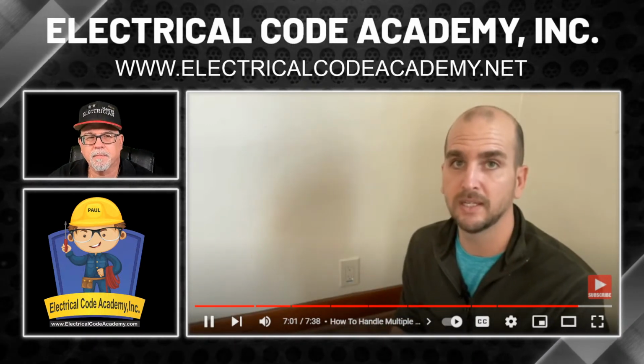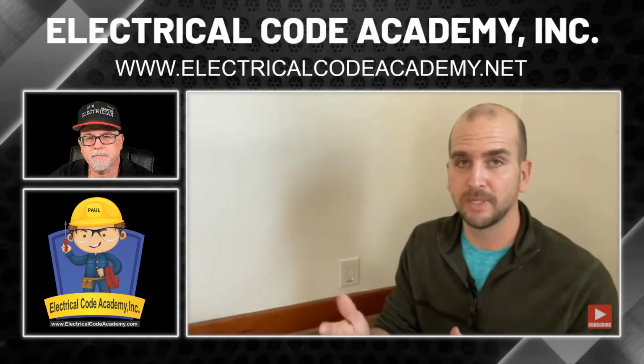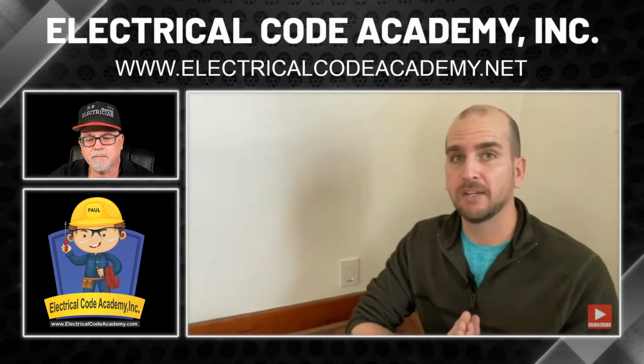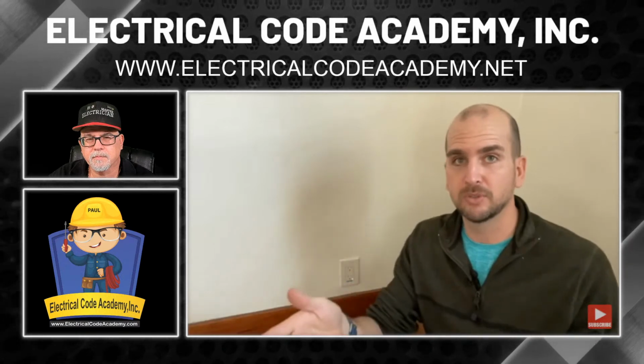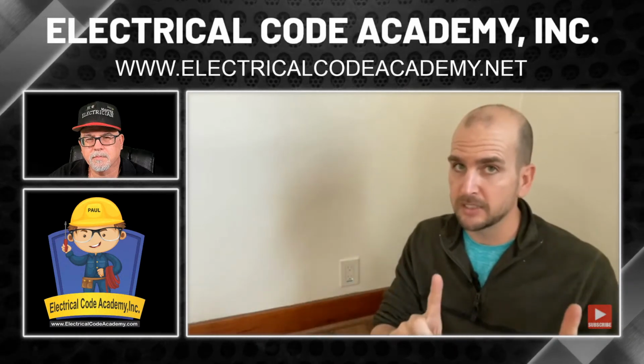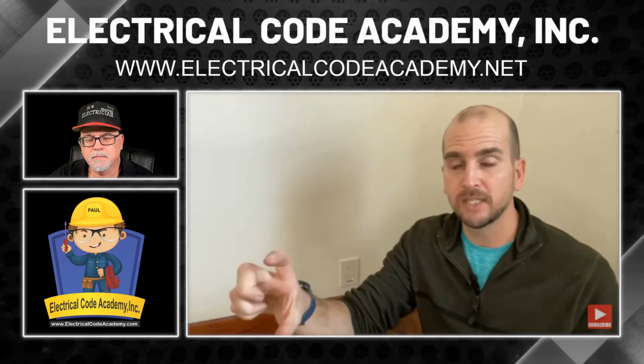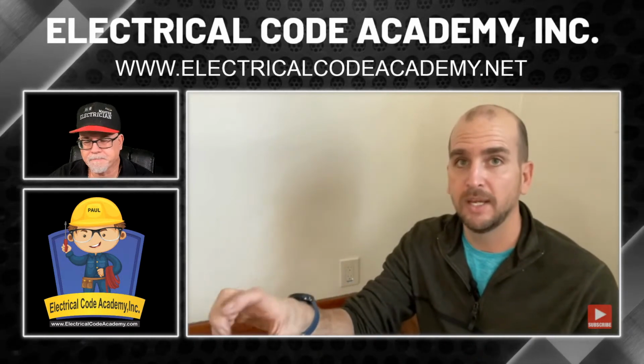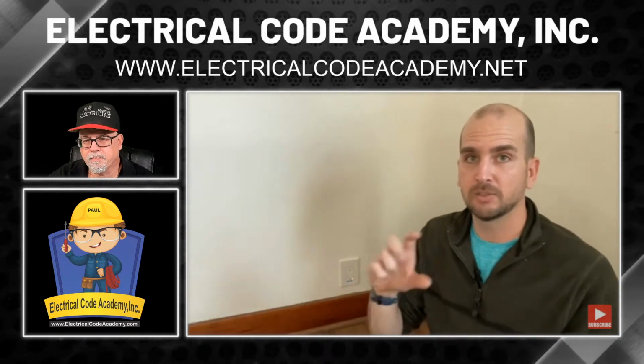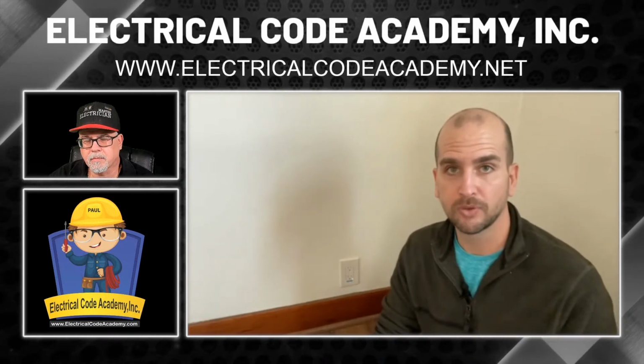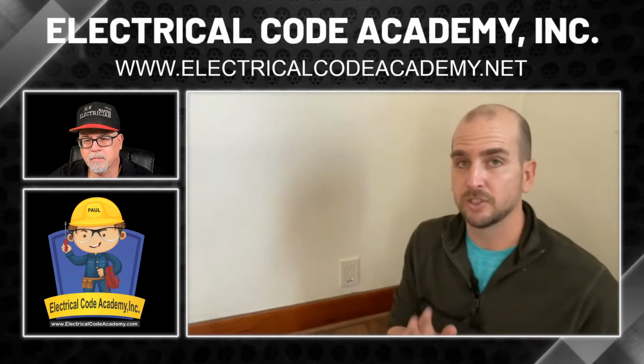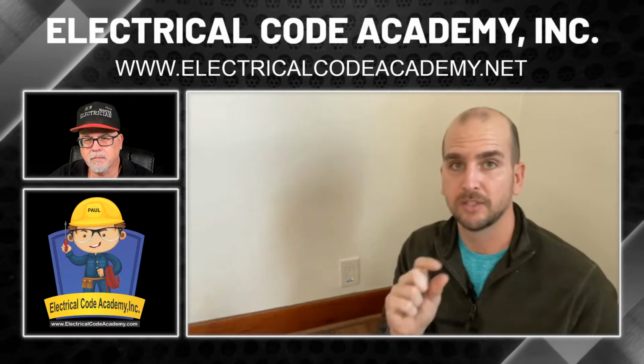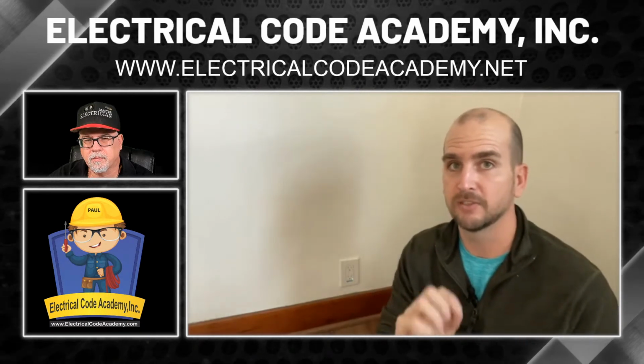As opposed to a GFCI. Now again, getting a little more complex, but I just wanted to let you know that if you have 3 or 4 receptacles in a room, there is a possibility if you install a GFCI at the starting receptacle that you could just install standard receptacles at the other 2 or 3 and you would be covered. Now you still will need to label that there's no equipment ground on that faceplate to follow NEC.